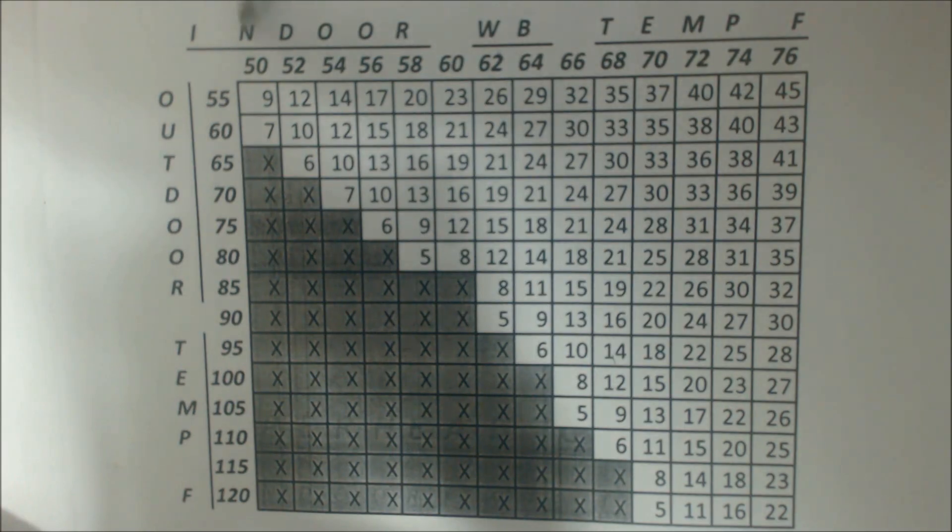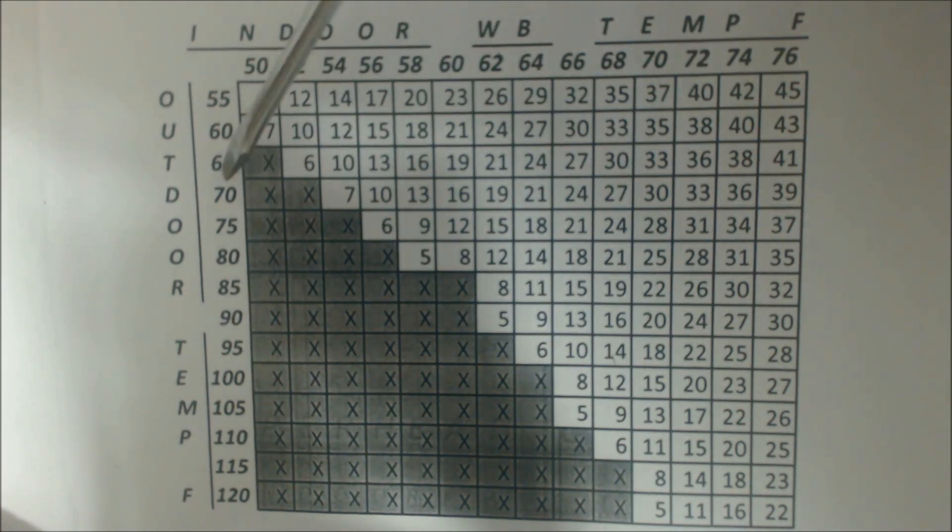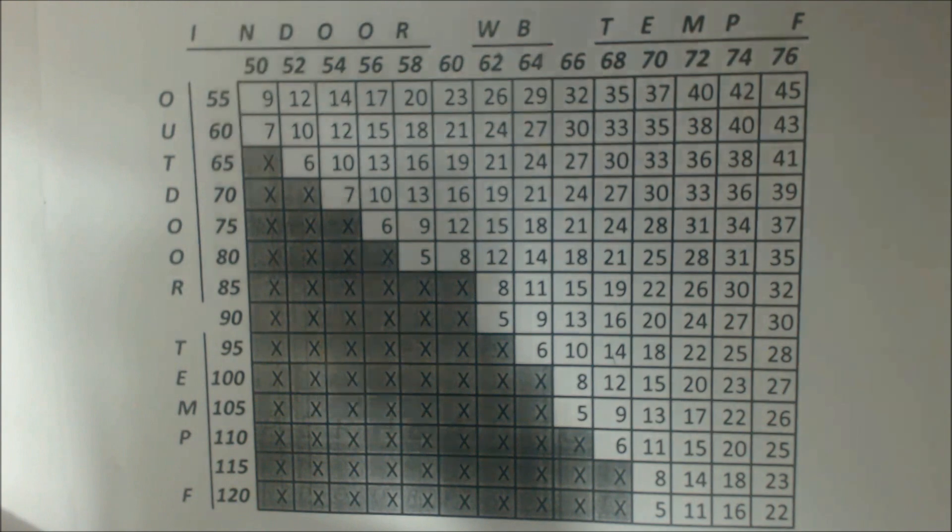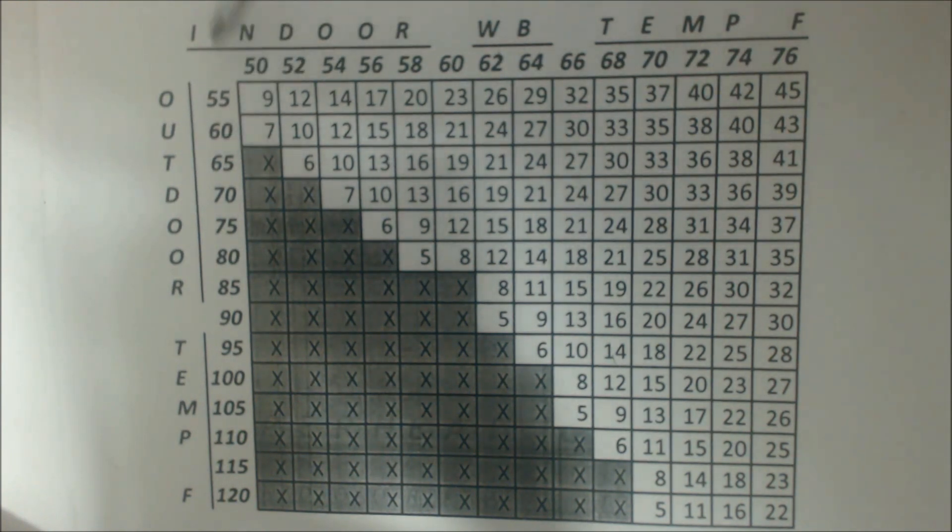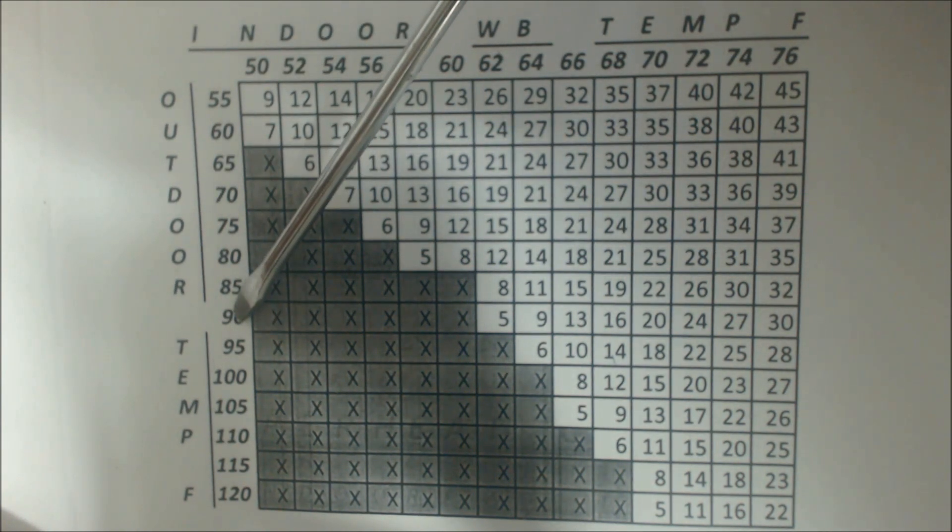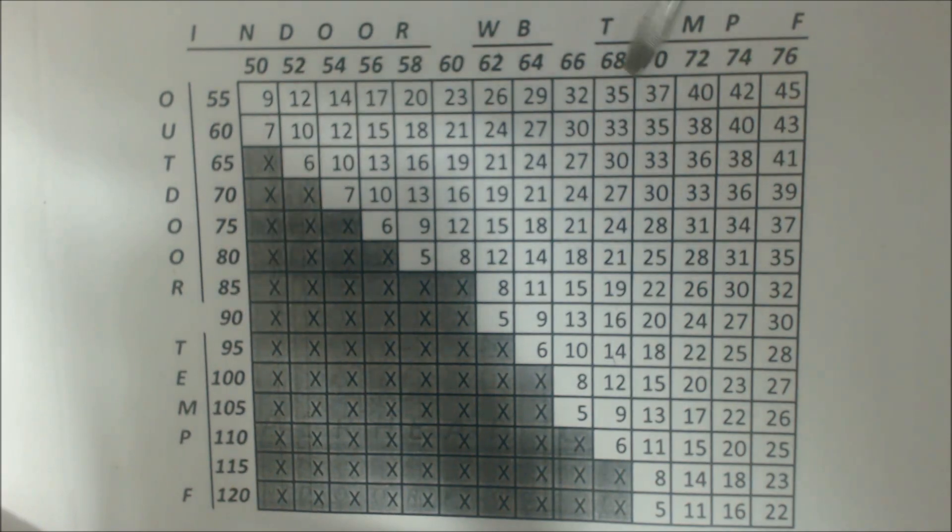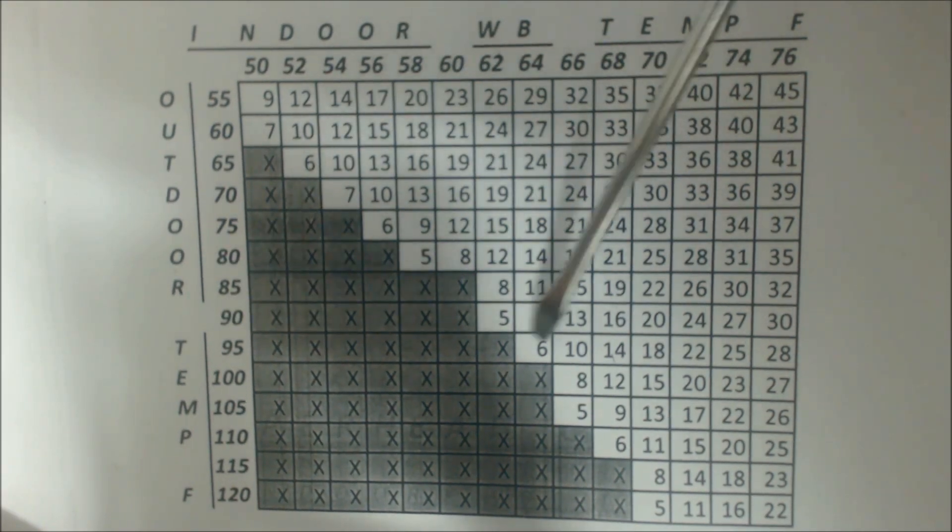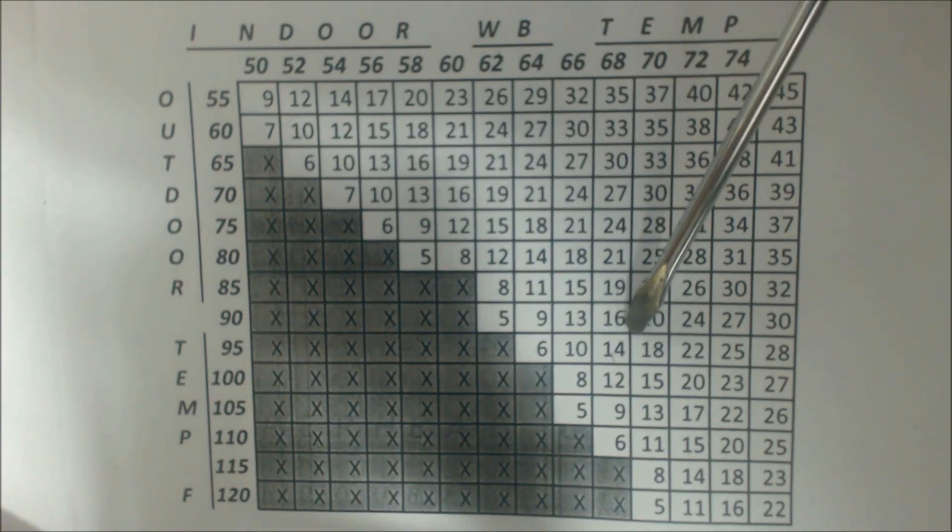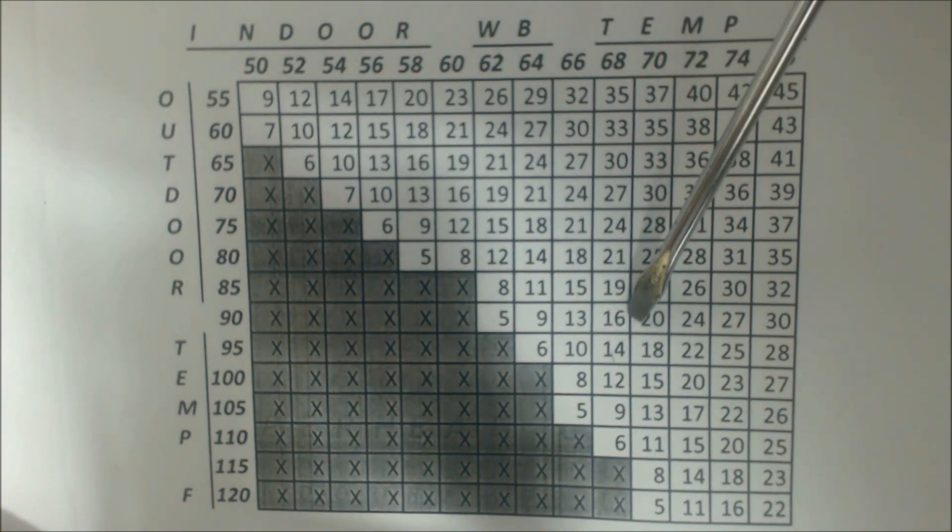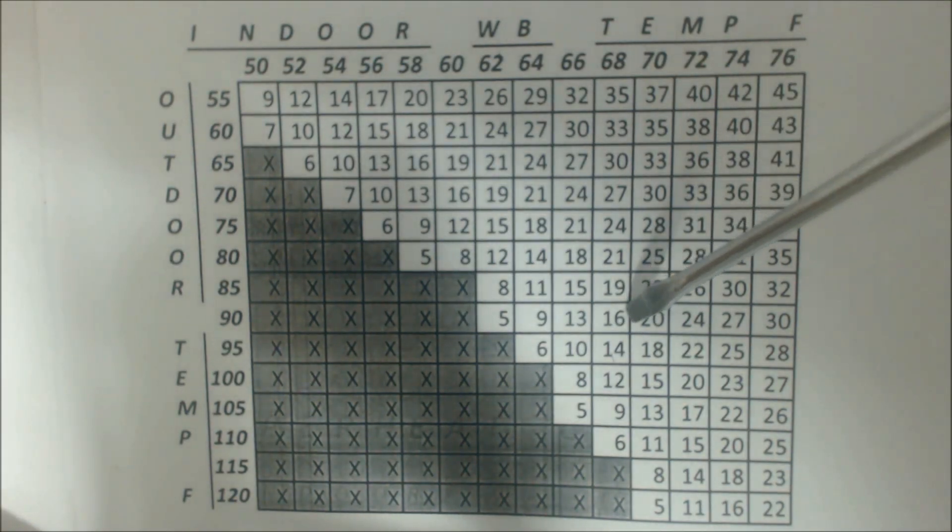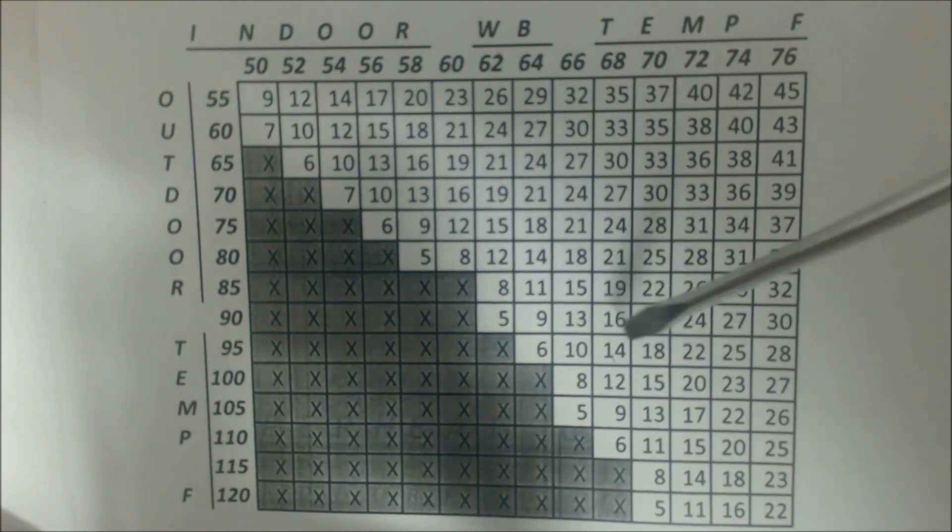Let's do a couple more and then I'll give you a screenshot of this at the end here. So let's just say it is 90 degrees outside and say it's 68 degrees wet bulb. Let's follow this over, 90 degrees, and we follow it over and we find 16 degrees of superheat as our target superheat. That's what we need to charge the system to.